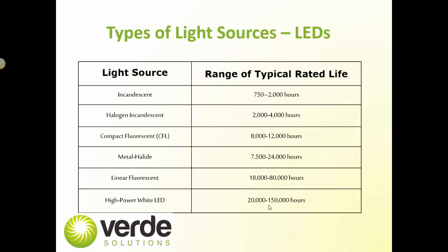And just again to give you a frame of reference, if you put these in a school that maybe runs 4,000 hours a year, and you have something that will last you 80,000 hours, that's 20 years. That would be the useful life. So that's something that we always tell our customers about LED.